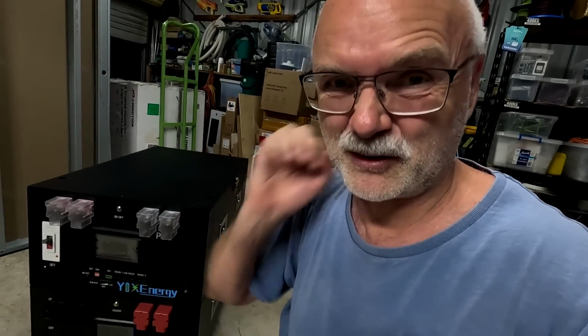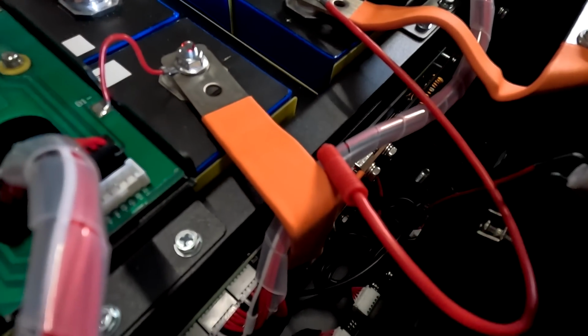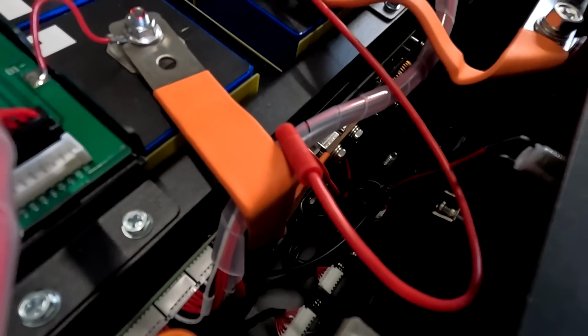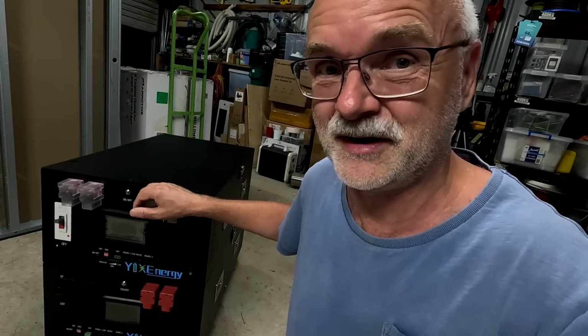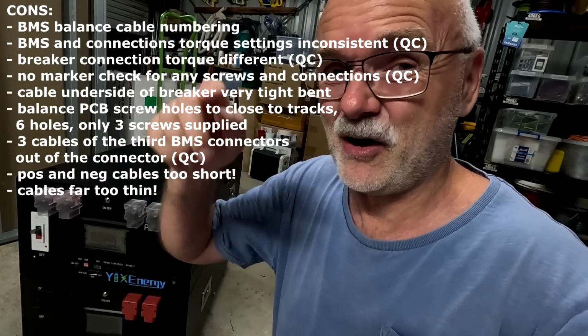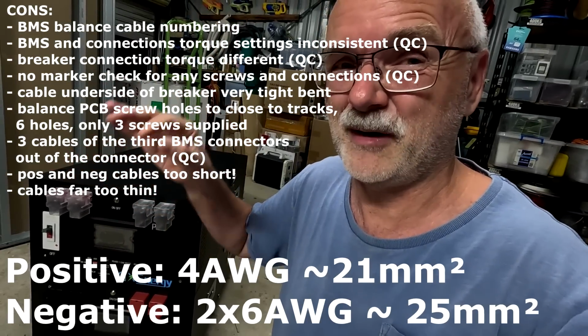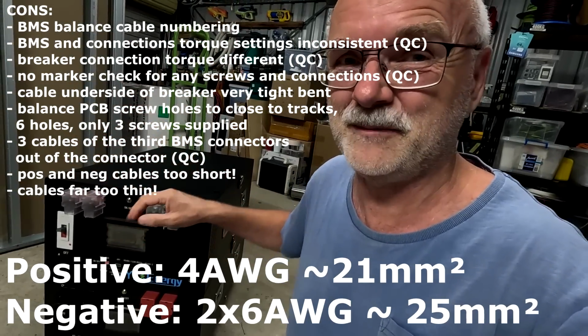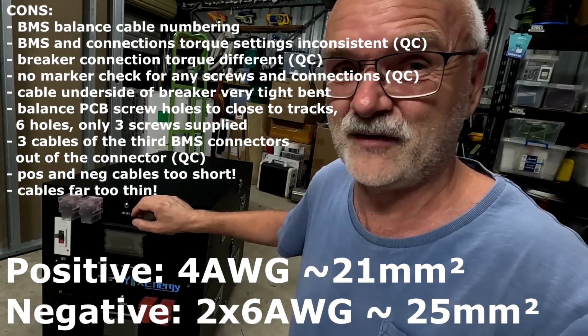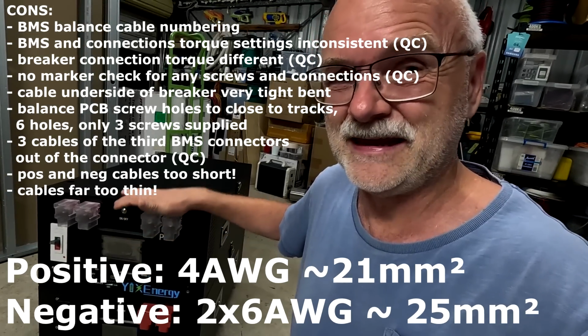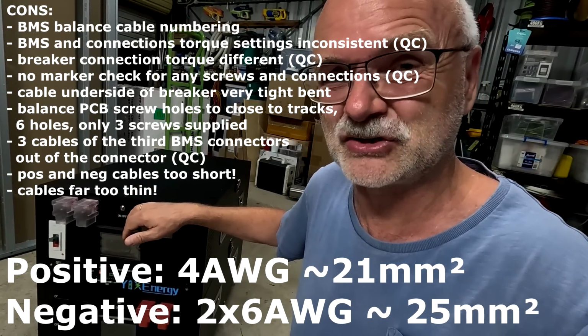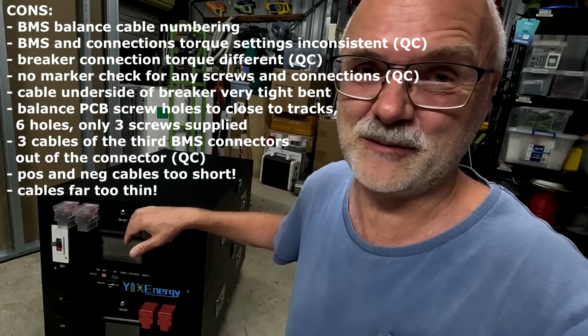It's a bit of a shame because the previous box had these flexible bus bars inside, and they have a far higher carrying capacity than these silicone cables they have put in now. But guys, let me know in the comments down below what you think about a 21 or 25 millimeter cable for 250 amps. Even though they are short and made from silicone insulation, again, I don't agree with that.